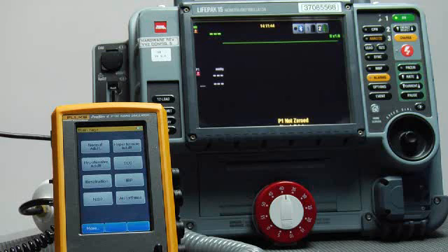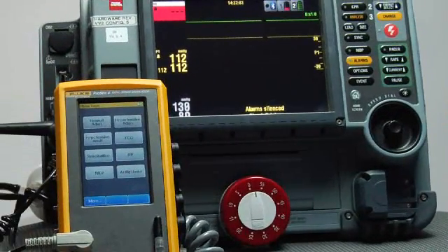The biomed brings the ProSim 4 to the location of the patient monitor and simply turns on the patient monitor, makes sure that the ProSim 4 is connected in place of the patient, which we have already done, and then at that point the time starts. We believe that you can do a go, no-go assessment of the patient monitor within 60 seconds. So we've responded to the cry for help from the clinical unit.